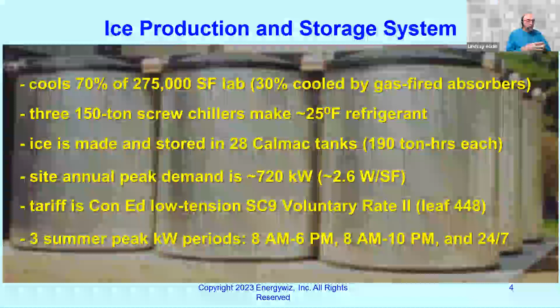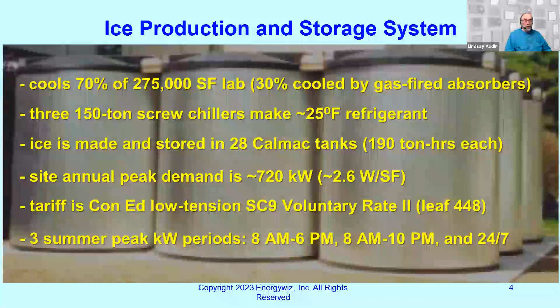Now, most of you in typical buildings will have the same peak demand for all 3 because it's probably peaking at around 3 o'clock in the afternoon. But with thermal storage, you can shape the load, shape the way in which you handle your need for cooling by looking closely at how you can adjust other loads in the building, other loads of your mechanical systems, so that you minimize each of these 3 peak demand charges and reduce peak load on the grid. One of the ways I found this can be done more easily is through load profiling using interval data.